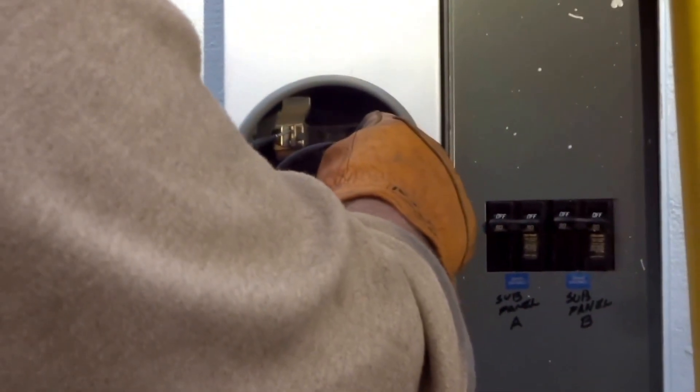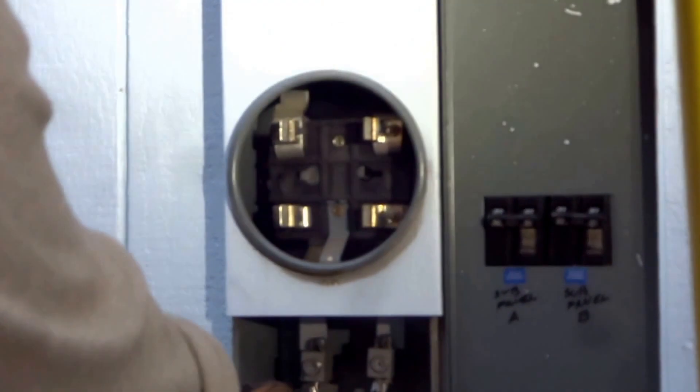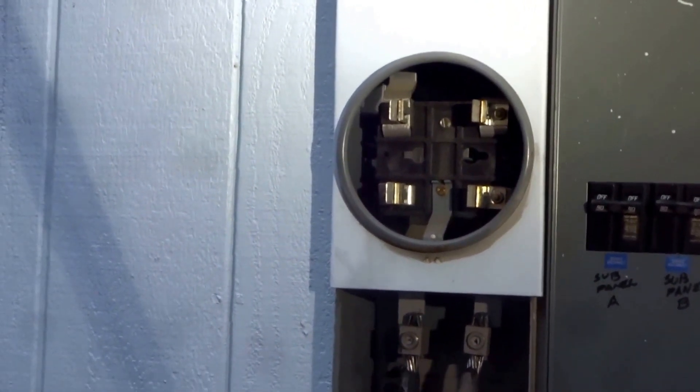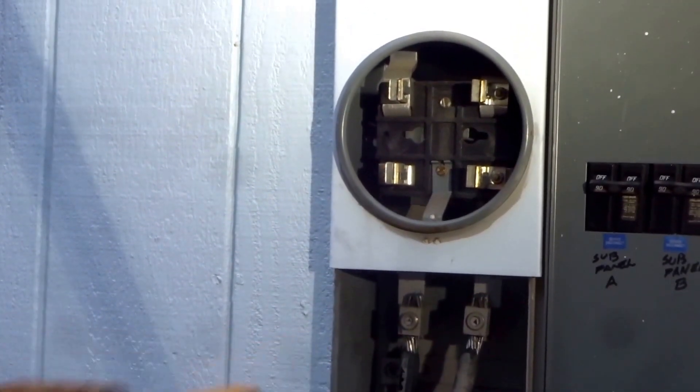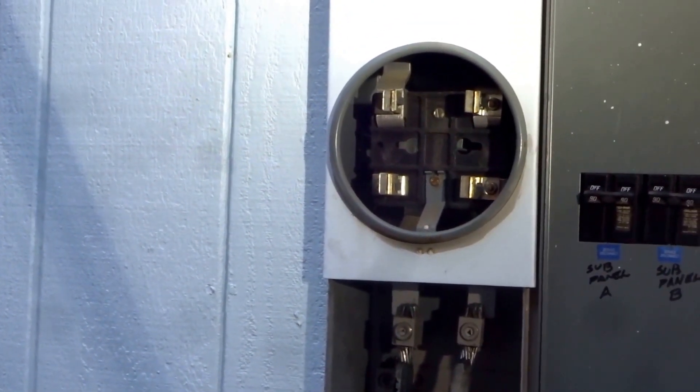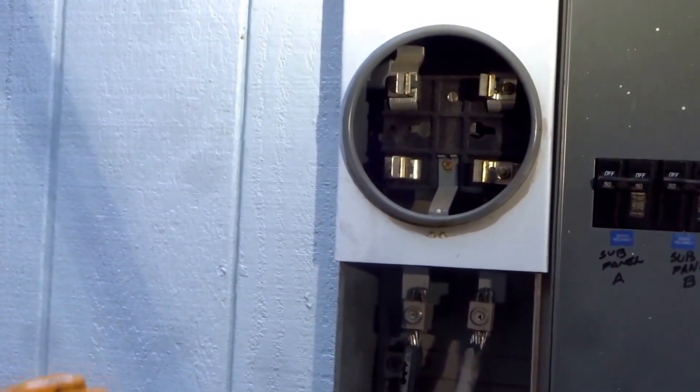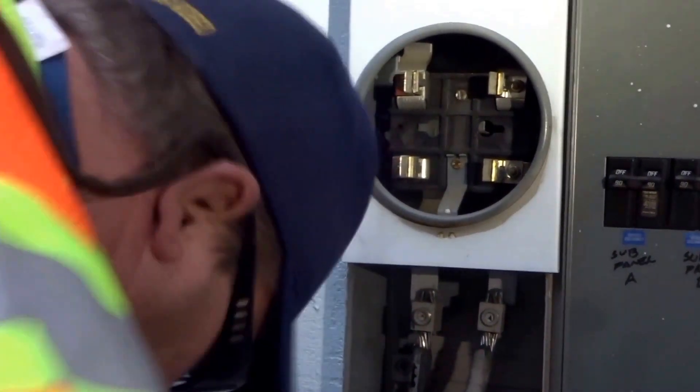So you got 239 volts here. I mean, that's good voltage. That's a problem. It shouldn't, cause it's not a solid connection. I shouldn't be able to move it like that. And I can't tighten it anymore because the lug, I don't want to break it. Cause I'm scared I'm going to break it cause it's moving the way it is. You've seen it. You put your hand on it. I want you to feel it.